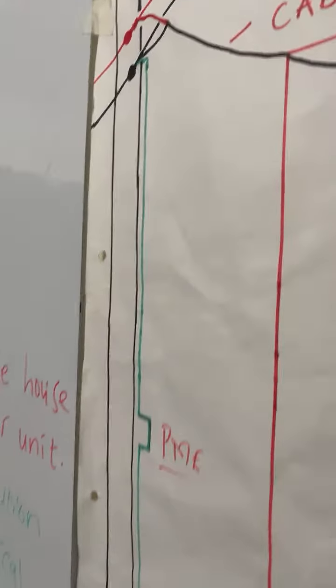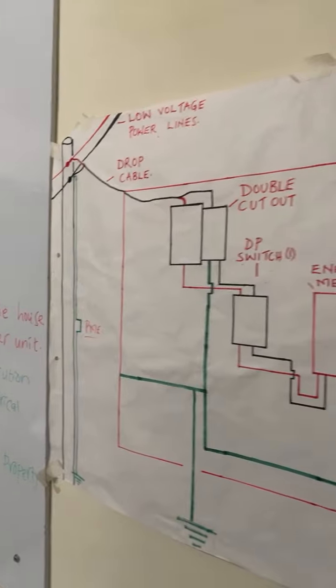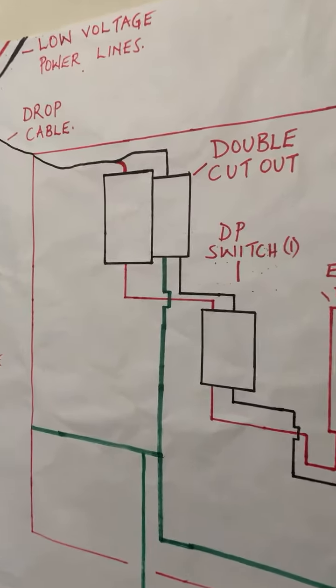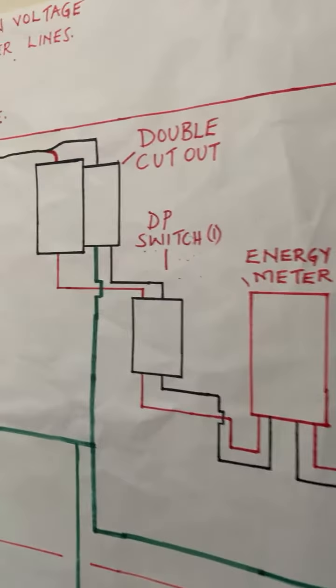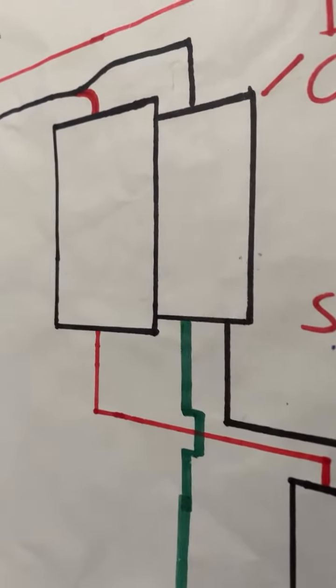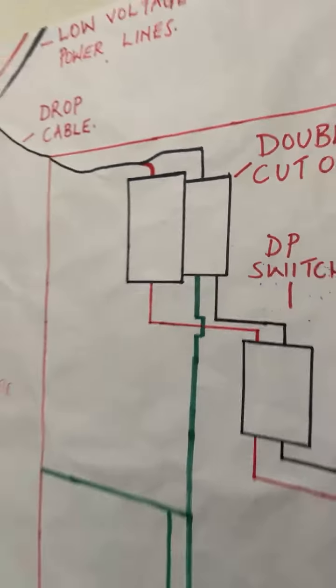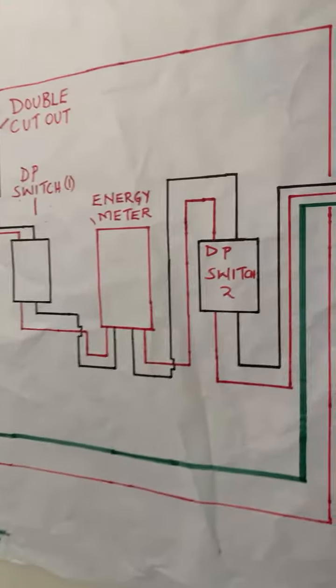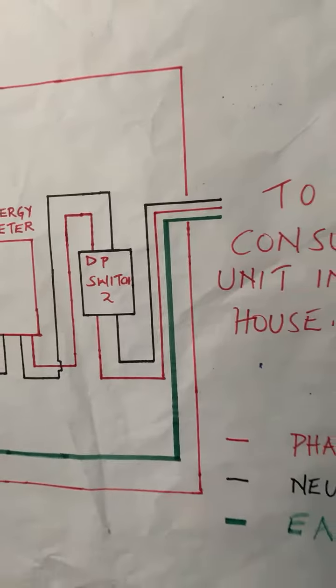Earth. We'll be talking about the PME. PME is the connection at the immediate pole that is serving your meter box with power. We'll also be touching on how earthing is bonded with the neutral at the cutout, and we also talk about the energy meter flow.